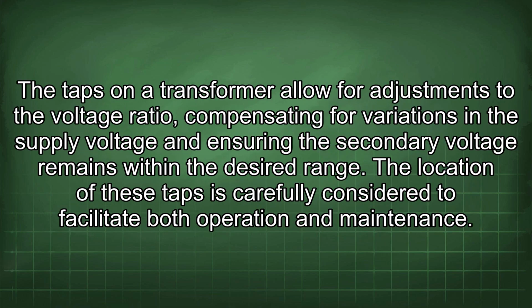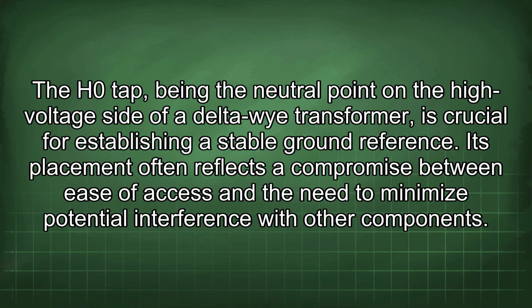The taps on a transformer allow for adjustments to the voltage ratio, compensating for variations in the supply voltage and ensuring the secondary voltage remains within the desired range. The location of these taps is carefully considered to facilitate both operation and maintenance. The H0 tap, being the neutral point on the high voltage side of a delta-wye transformer, is crucial for establishing a stable ground reference.